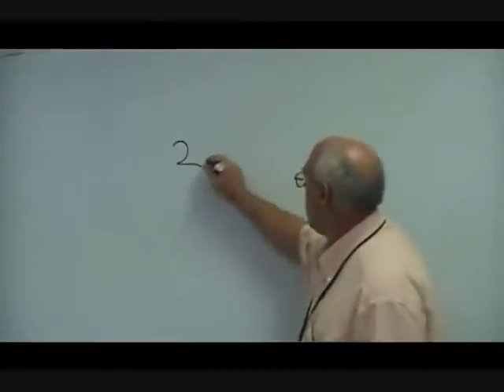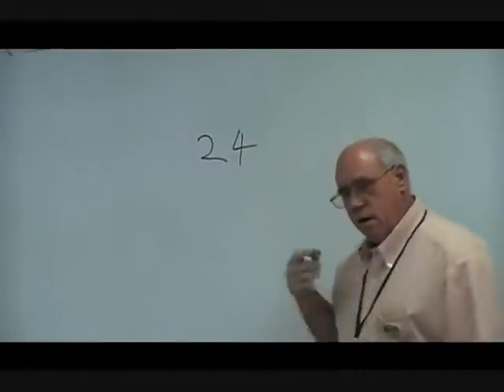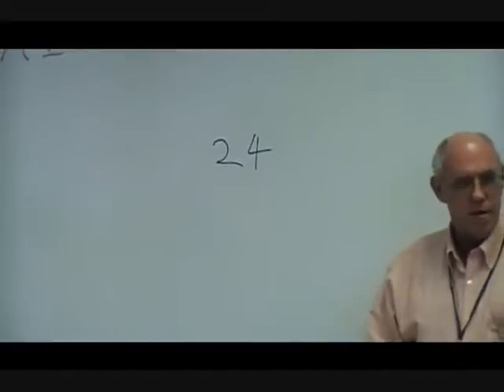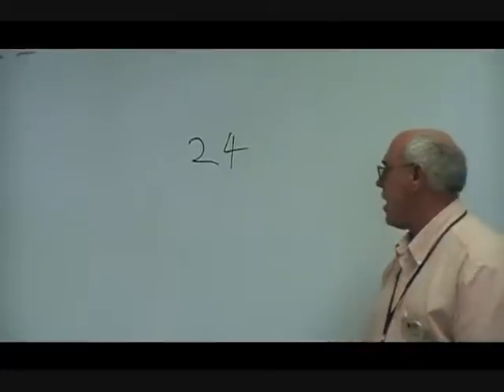Transformers are rated in VA — that's volt-amperes. One way you can determine the capacity of a transformer is through Ohm's law: P equals I times E, which is current times voltage. For example, with a 24-volt output, standard transformer ratings would be 20 VA or 40 VA — those are pretty standard, though other ratings exist.